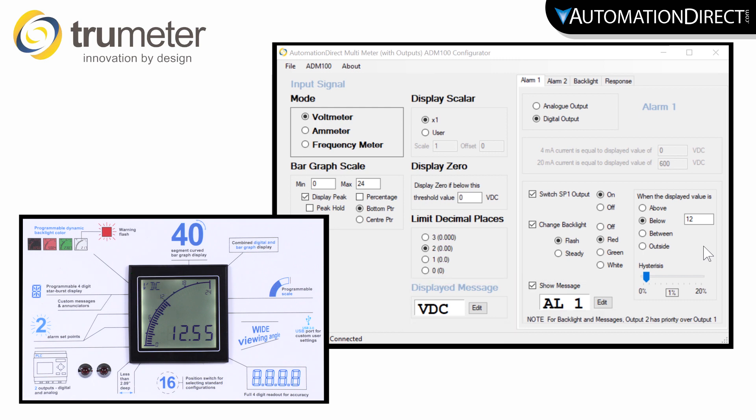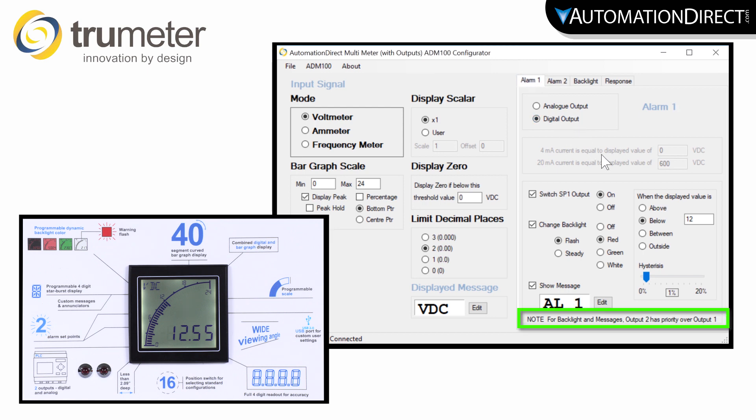That sets up alarm 1. Alarm 2 is completely independent but sets up just the same. But make sure to note that alarm 2 condition has priority over alarm 1. This just means that if alarm 1 and alarm 2 are active at the same time, alarm 2 is the one that will display on the panel.